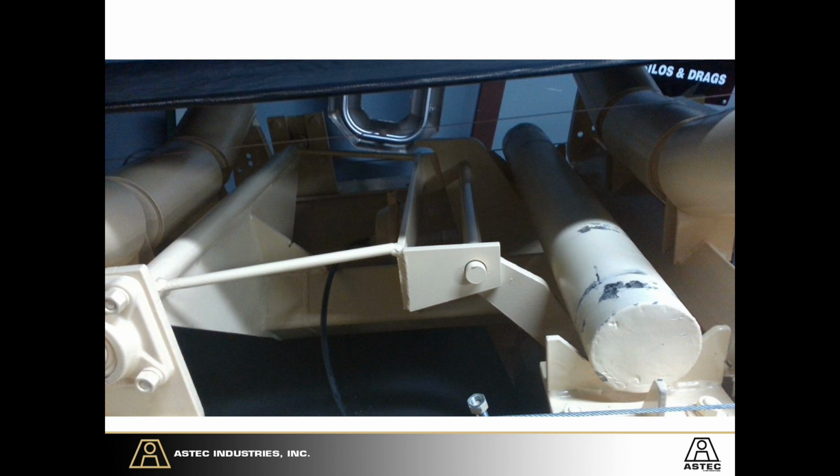As we push through and look at this, we can see here this is the device for the test weight. You can have a test weight here. It gives the operator the ability to do a quick test to see if the calibrations are in. There are some pinch points and things here you need to be aware of. Also, when you do an inspection and you remove these wing guards, this is also areas for material to fall in, so also look for that.